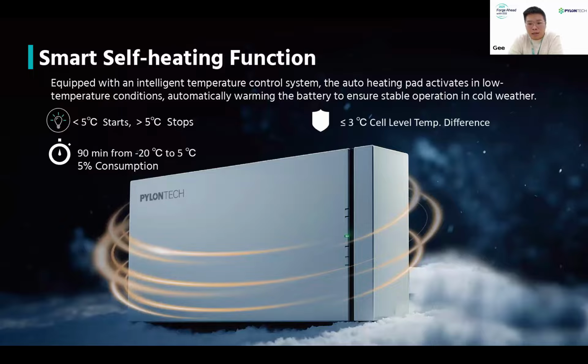When you black-start the battery - let's assume you've just installed it in a very cold condition, so the environmental temperature could be like minus 20 Celsius degrees - the first time you launch this product, it needs to warm up to 5 Celsius degrees. This will take around 90 minutes and consume around 5% of the SOC to heat itself up.